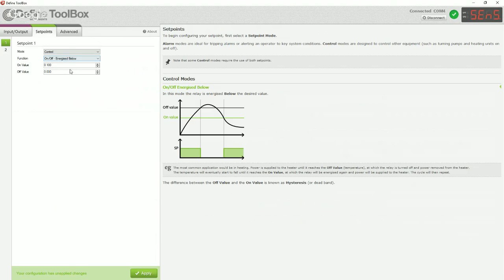So we'll select below, and then there's an on value and an off value. So let's say we want the motor to turn on when the level drops below our 6 milliamps, and we want it to turn off again when it gets to 12 milliamps. Now we can set up scaling as well, so we could set up on the input tab the scaling so that we don't have to put milliamp readings in here. So we could set it up and say 4 milliamps is 0 liters and 20 milliamps is 10,000 liters, and then we can set up these controls in a liter value in our engineering units, so it's much easier for us to understand. But for the moment, we'll just do it like this, and we click apply. That is now set up and ready to go. So that's the most basic one.